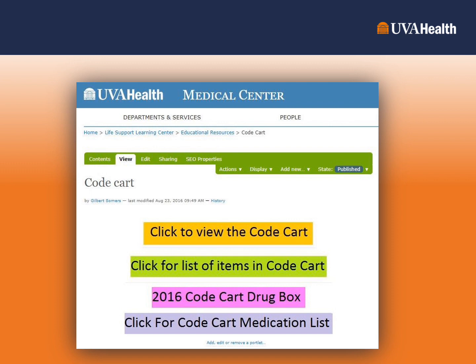Do you just hook it onto the pump tubing, the Alaris pump? That won't work. It'll cause damage to the pump tubing. There are restrictive devices, and it won't be able to get the fluid in fast. So if a physician ordered 1 liter of fluid now, and you put it on the Alaris pump, the fastest you can give it is 999 mL an hour. So you would need to switch out that tubing for surgical tubing, which in our hospital are 20 drop sets that have no restrictive devices. Therefore, the fluid would go in quickly, and you could hook a pressure bag to that. So knowing what's in the code cart will help you in an emergency.